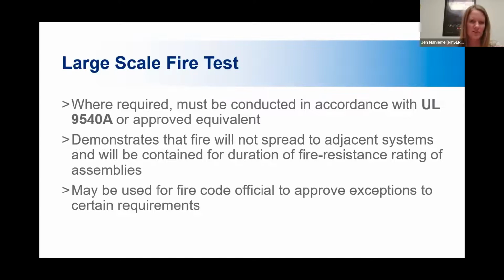Based on the results of that large scale fire test, the fire code official can approve exceptions to certain requirements all throughout the code. And those are all outlined, like this is a part where, based on the results of the large scale fire test, the code official has the authority to make those sorts of decisions. The large scale fire test is basically a laboratory forcing some of the systems into thermal runaway, purposely trying to make them catch fire, and then watching what happens.